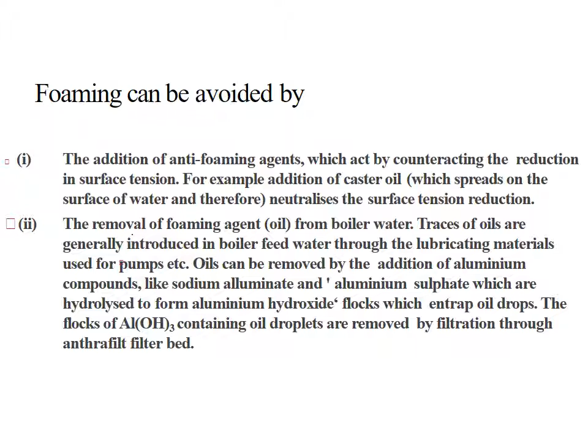Such oils can be removed by the addition of compounds of aluminium like sodium aluminate as well as aluminium sulfate. When aluminium compounds like sodium aluminate or aluminium sulfate are added to the boiler water, they hydrolyze and form aluminium hydroxide. Aluminium hydroxide precipitates out in the form of floc, which entraps oil droplets. The floc of aluminium hydroxide containing oil droplets is removed by filtration through an anthracite filter bed.